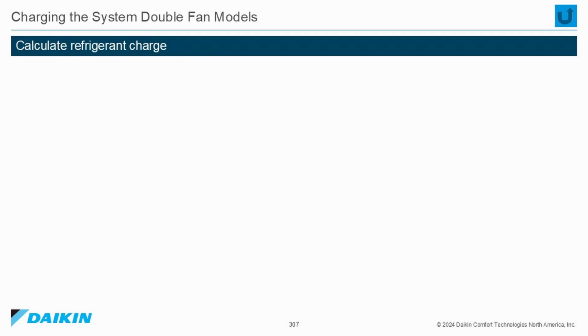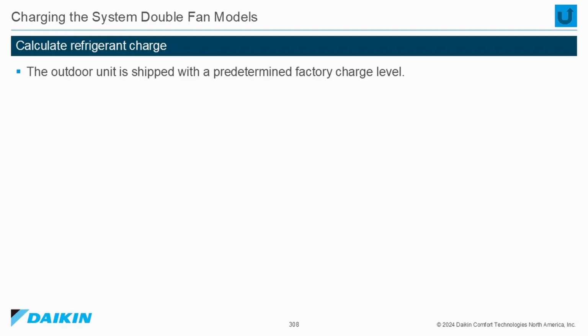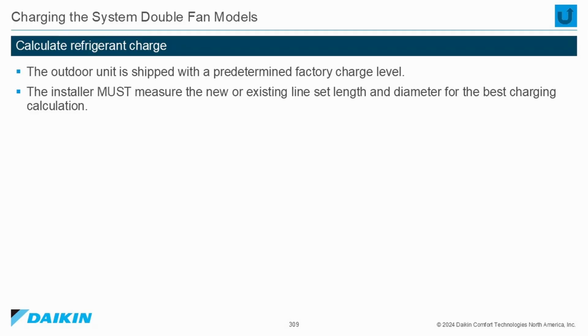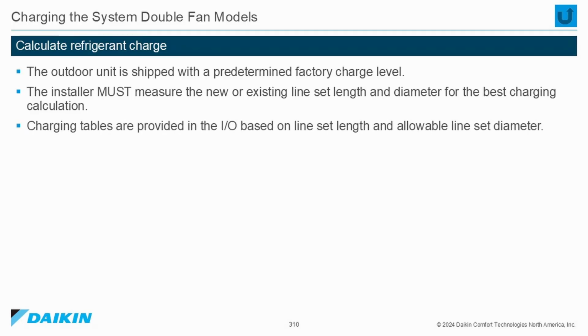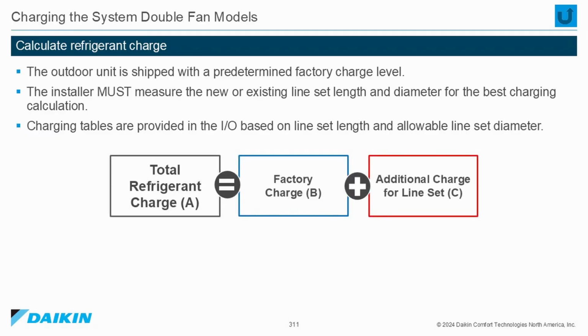Charging the system, double fan models. Calculate refrigerant charge. The outdoor unit is shipped with a predetermined factory charge level. The installer must measure the new or existing line set length and diameter for the best charging calculation. Charging tables are provided in the installation operation manual based on line set length and allowable line set diameter. Total refrigerant charge, A, equals the factory charge, B, plus the additional charge for the line set, C.